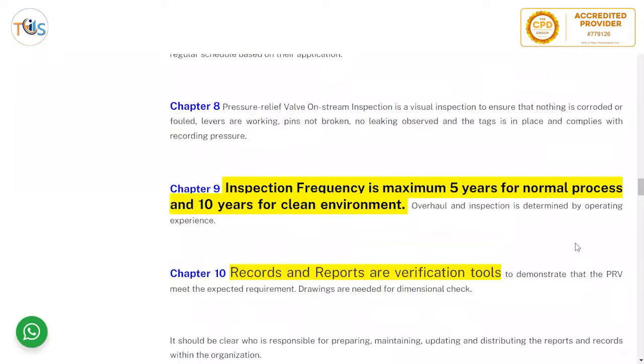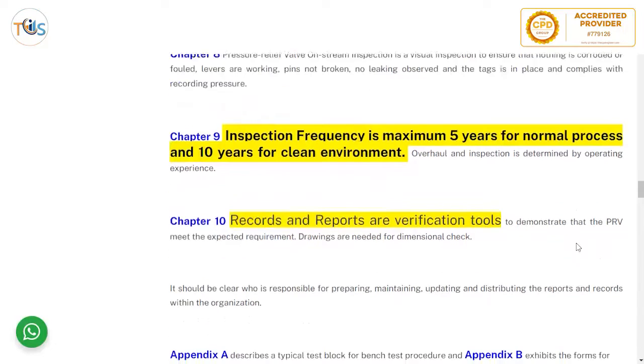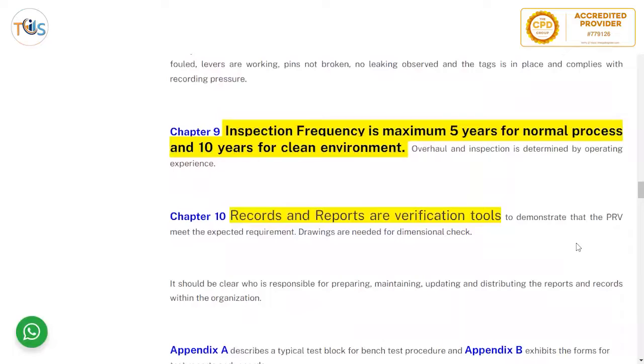Pressure relief valve on-stream inspection is a visual inspection to ensure nothing is corroded or faulty — levers are working, pins not broken, no leaking observed, and the tag is in place and complies with the recorded set pressure. Inspection frequency is a maximum of five years for normal service and 10 years for a clean environment. This is a potential exam question regarding inspection frequency for normal versus clean service.